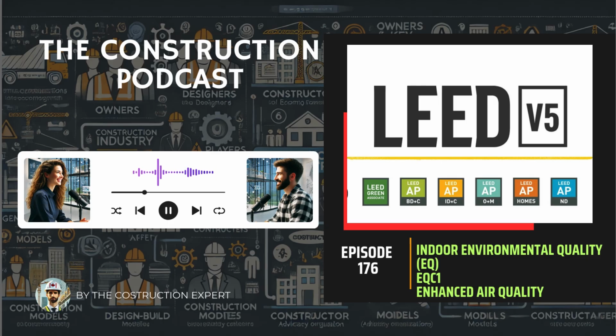Just to quickly recap the key takeaways for everyone listening. Achieving this Enhanced Indoor Air Quality Credit, EQc1, requires first exceeding that ASHRAE 62.1 2022 baseline, EQp2. Then, you have to choose one of two pretty demanding paths. Path 1, option 1, is the dilution strategy. Commit to at least a 15% minimum increase in breathing zone outdoor air ventilation, delivered to 95% of occupied spaces. Go up to 30% for exemplary performance, but brace for the energy impact.